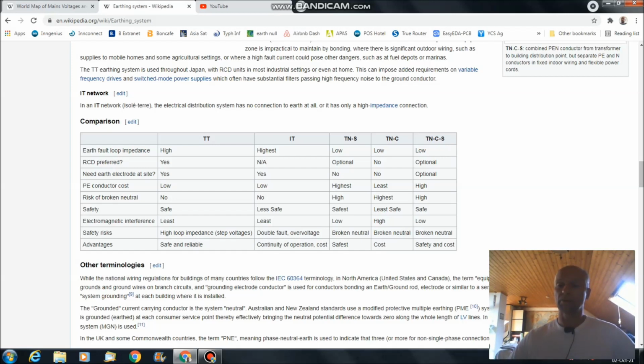So which one would you choose if you go for installation? As I said, I would go for a TN-S system because we have a very low earth fault loop impedance, because the return current will go through our circuitry back to the inverter and then through our bonding wire directly to the neutral of the inverter. So this is, of course, the lowest earth fault loop impedance possible. And for the secondary part, if a human touches a hot wire somewhere, then it is still the best version there. Yeah, so you see the risk of TN systems is always the broken neutral. From the advantages, it is the safest system that we can choose.